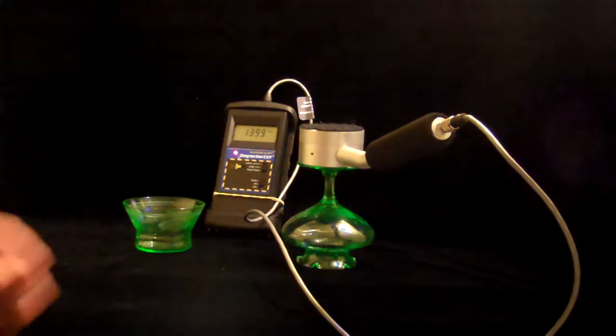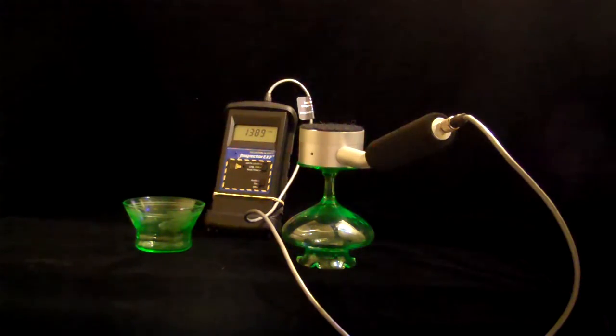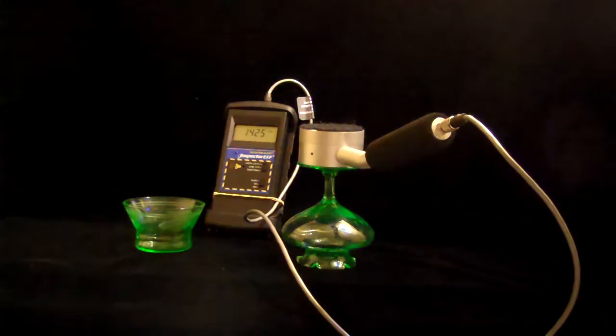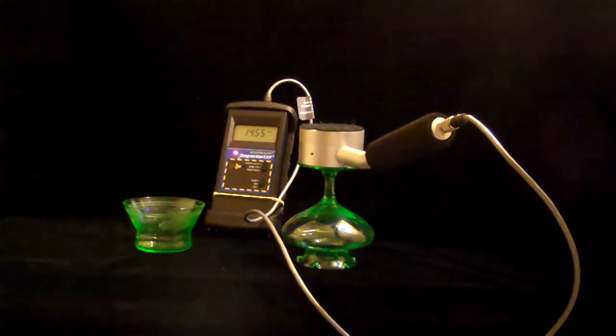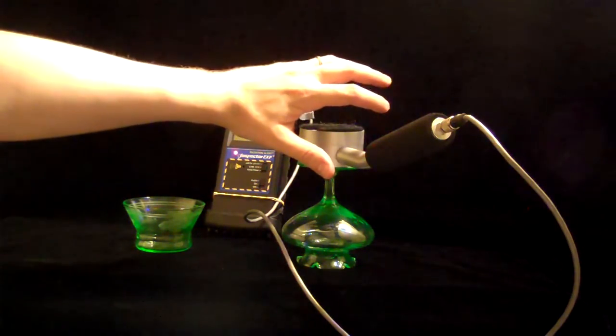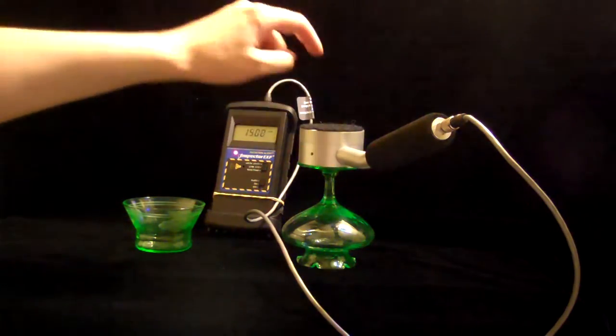The point of the matter is, the Geiger counter has the ability to detect different types of radioactivity at different efficiencies. Technetium-99-M, for example, the gamma rays coming off of it, less than 1% efficiency, meaning that if I see 1000 counts on this from somebody who has Technetium-99 treatment, in reality, it could be 100 times or more, but I just can't detect them because they go through the unit.